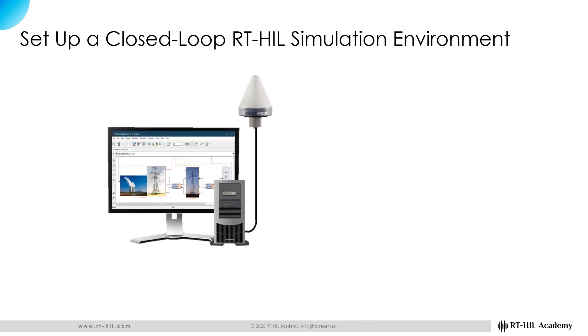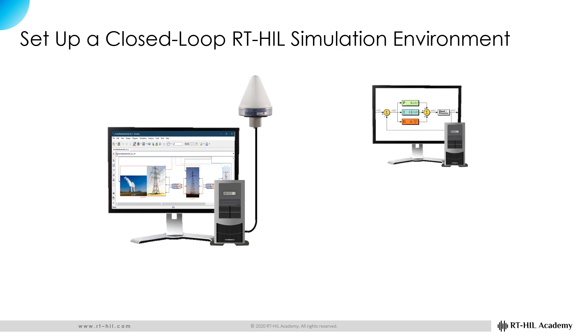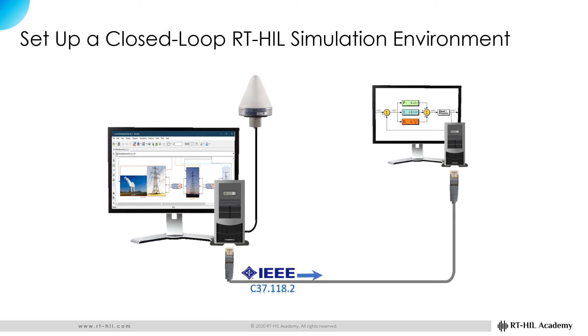Now that you know real-time simulators can be configured to act as synchrophasor client and server as well as Modbus master and slave, you can set up a closed-loop RT-HIL simulation environment by use of IEEE C37.118.2 and Modbus protocols. For example, you can have a real-time simulator simulating your system and acting as a virtual PMU to send synchrophasor data to a controller running on another real-time simulator. The controller, in turn, communicates with actuators in the simulated system through Modbus.